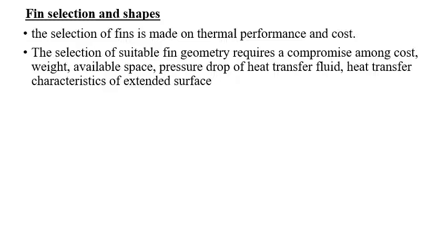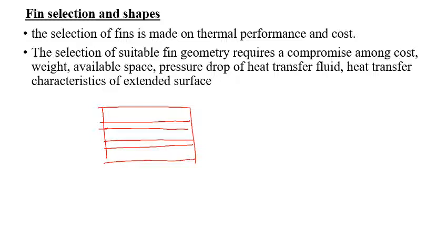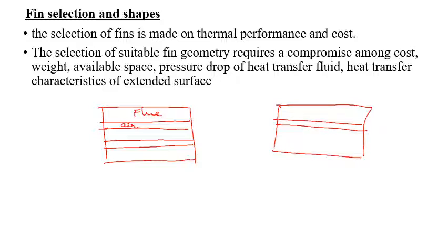In the earlier practice, in the air preheater, they used to have the air in the tube surrounded by the flue gas. By this, the operation was comfortable and there was no pressure drop. But in the recent change in design, they have the flue gas inside the tube and air surrounding it.